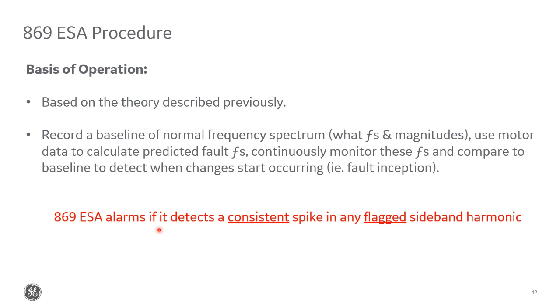The long story short version for you to remember of what we do is that we record a baseline of the normal healthy motor frequency spectrum. Then we use the motor data provided to calculate the predicted fault frequencies, as we just discussed. Then we continuously monitor these frequencies and compare them to the baseline data to detect when changes start occurring, aka when a fault starts. If we detect a large enough change for a long enough period of time, which are 2 of the key settings that we set, then we alarm on ESA.